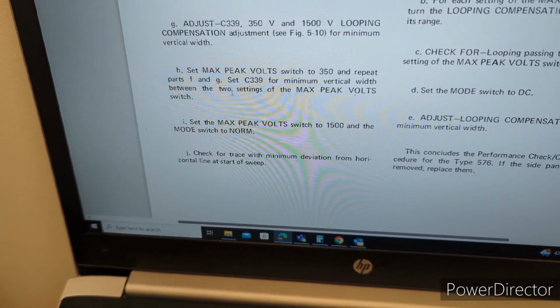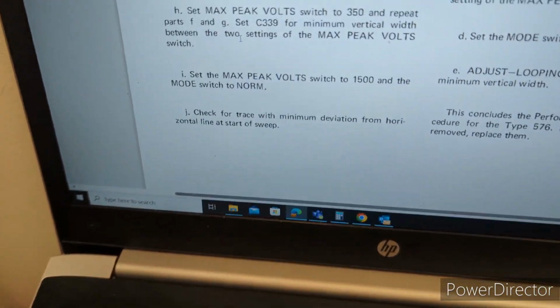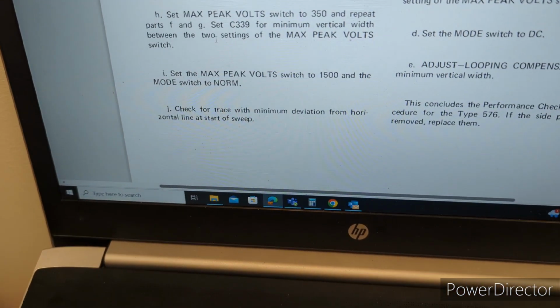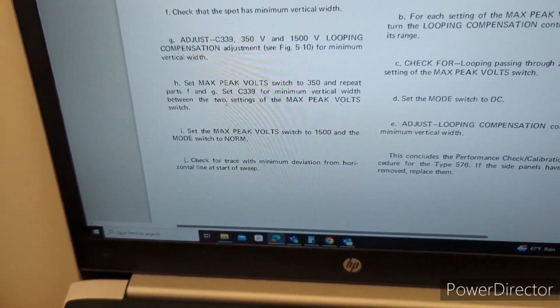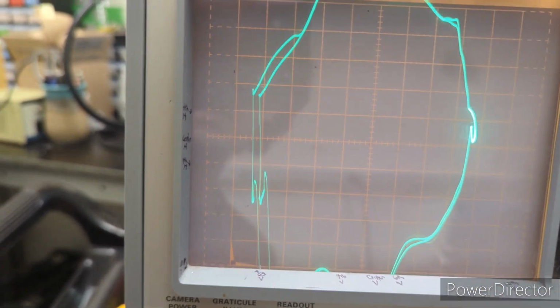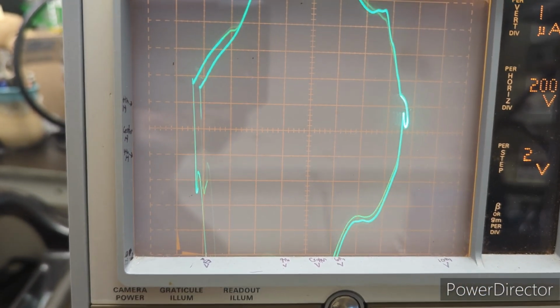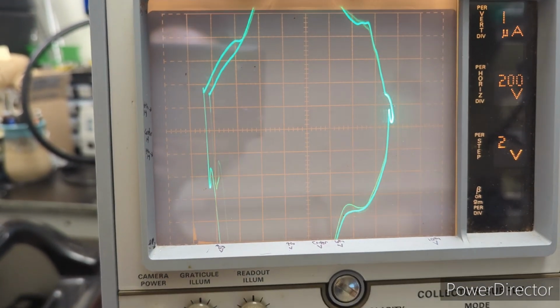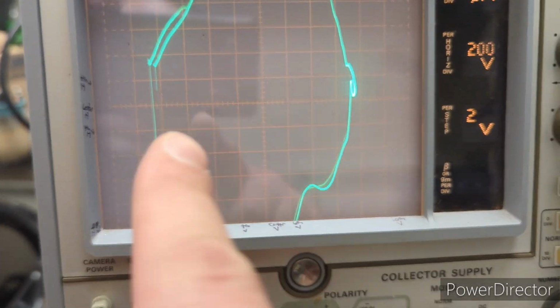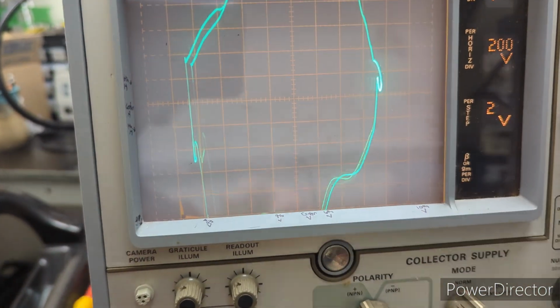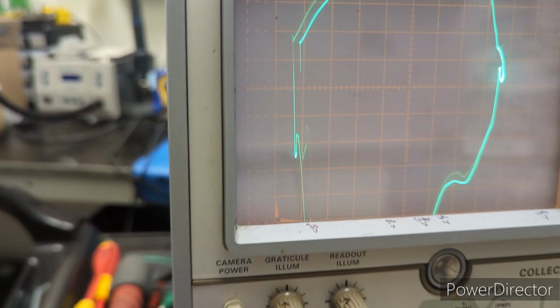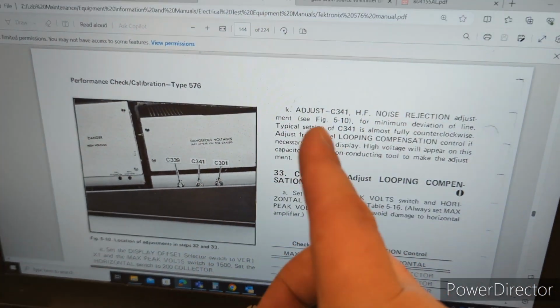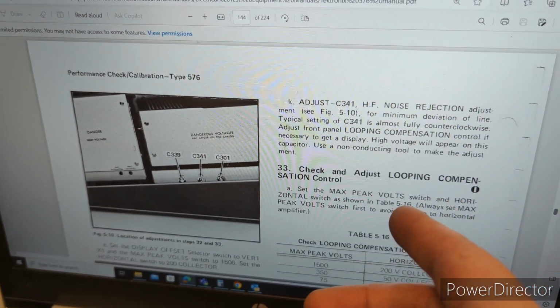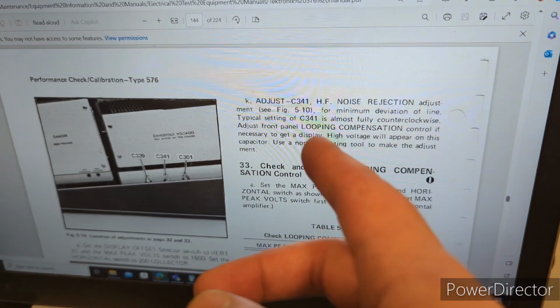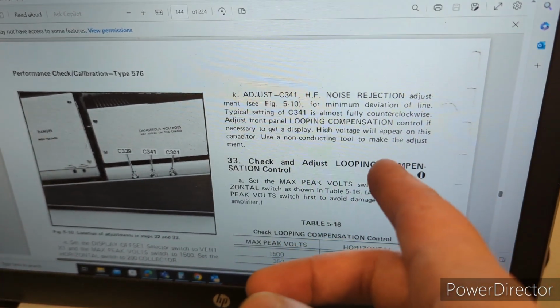okay, set the max peak volt switch to 1500 and then mode switch to norm. Okay, so we've done that. And then it says check for trace with minimum deviation from the horizontal line at start of sweep. So minimum deviation from the horizontal line at the start of the sweep. I'm not really quite sure what they mean by that. Are they talking about the center horizontal line, which would be here? Maybe. But it goes on to say, if you need to make that adjustment, adjust C341, which is the noise rejection adjustment, for a minimum deviation of line. Typical setting of C341 is almost fully counterclockwise.